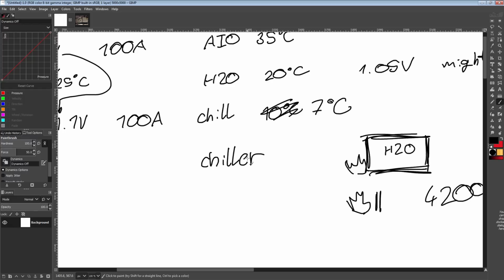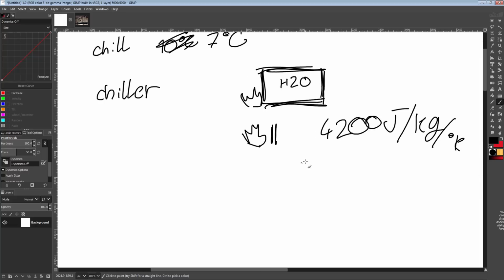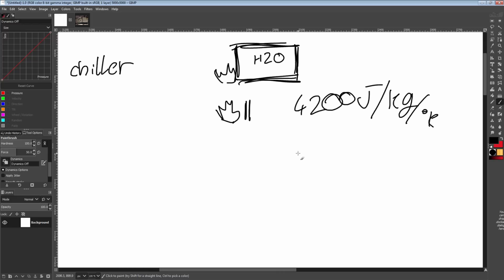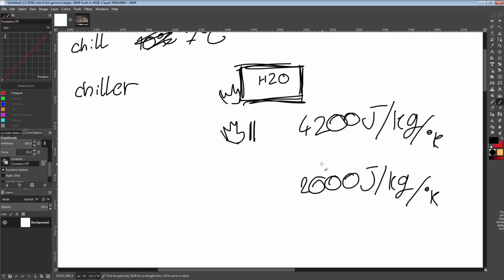The issue with all of those is that they don't have as much thermal capacity as water. I can't remember any alcohol thermal capacities off the top of my head, so let's say you have a theoretical liquid that's 2,000 joules per kilogram per degree Kelvin, and you mix it 50-50 with water. Now your thermal capacity is basically the middle ground between the two, which is about 3,100 joules per kilogram.